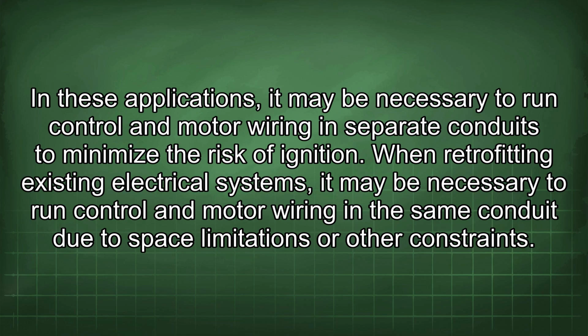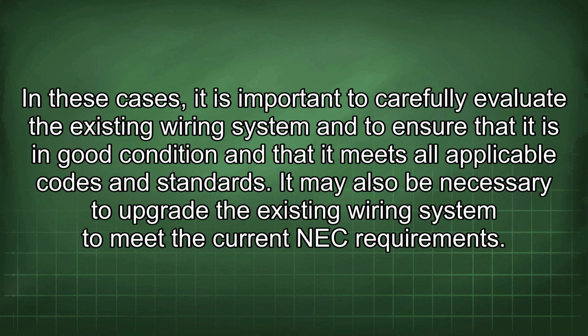When retrofitting existing electrical systems, it may be necessary to run control and motor wiring in the same conduit due to space limitations or other constraints. In these cases, it is important to carefully evaluate the existing wiring system and to ensure that it is in good condition and that it meets all applicable codes and standards. It may also be necessary to upgrade the existing wiring system to meet the current NEC requirements.